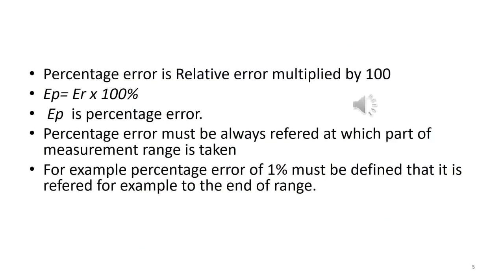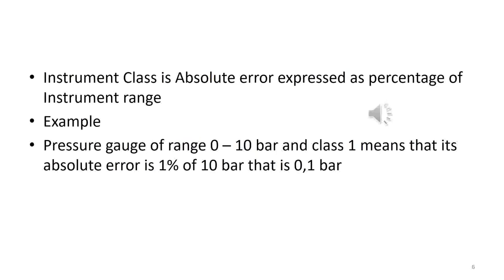Percentage error is relative error multiplied by 100. EP equals ER multiplied by 100. EP is percentage error. Percentage error must always be referred at which part of measurement range is taken. For example, percentage error of 1% must be defined that it is referred, for example, to the end of range. Instrument class is absolute error expressed as percentage of instrument range. Example, pressure gauge of range 0 to 10 bar and class 1 means that its absolute error is 1% of 10 bar, that is 0,1 bar.